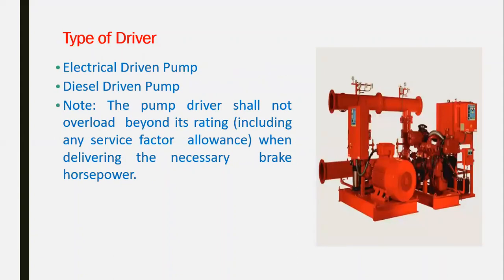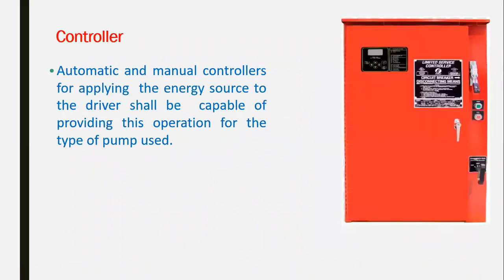The types of drive for the fire pump, as we said, are the electrical driven pump or the diesel driven pump. The pump driver should not be overloaded beyond its rating, including any service factor allowance, when delivering the necessary brake horsepower. Controller for the electrical panel: it has automatic and manual controllers, an automatic switch, and a manual switch for testing.